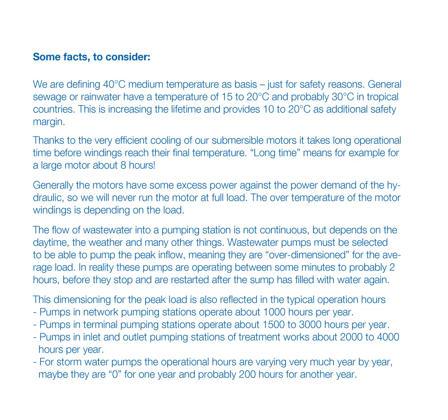Thanks to the very efficient cooling of our submersible motors, it takes long operational time before windings reach their final temperature. Long time means, for example, for a large motor about 8 hours. Generally the motors have some excess power against the power demand of the hydraulic, so we will never run the motor at full load. The overtemperature of the motor windings is depending on the load.